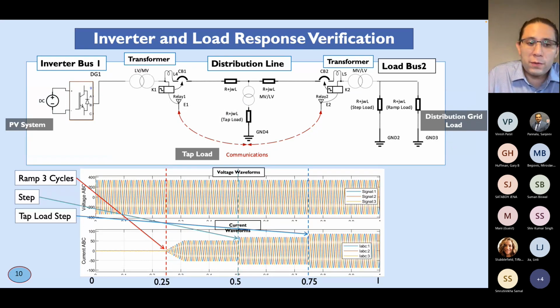So this is a subset of our four bus system grid that I mentioned before. Basically, this test was done to validate the response of the inverter in a normal setting, like in a distribution grid, where the inverter will go through different types of loads. So we try to test the most critical ones in this setting to validate the operation of the inverter itself. We tested here what is called a step load.